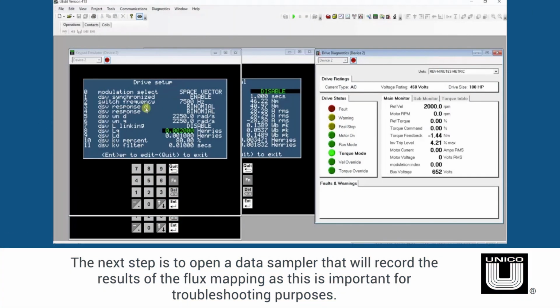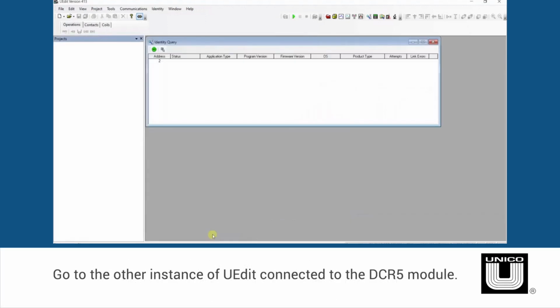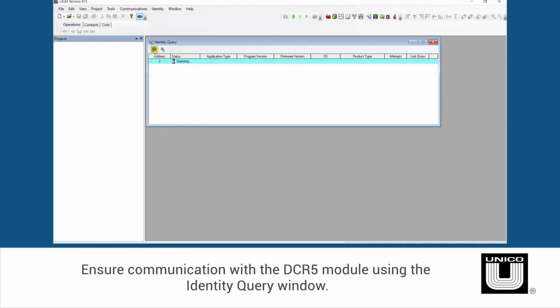The next step is to open a data sampler that will record the results of the flux mapping, as this is important for troubleshooting purposes. Go to the other instance of UEdit connected to the DCR5 module. Ensure communication with the DCR5 module using the Identity Query window.